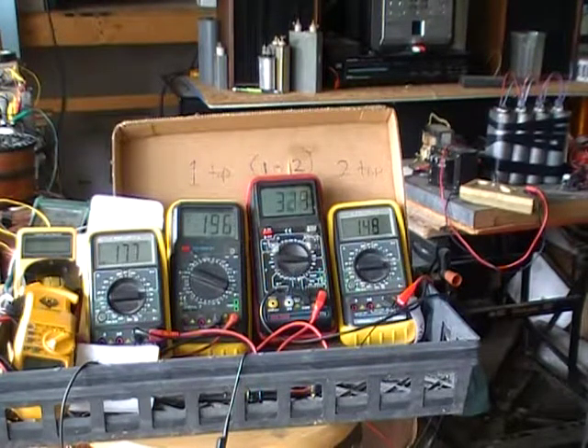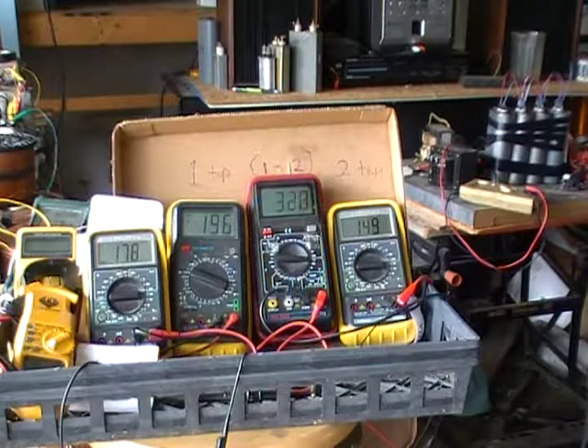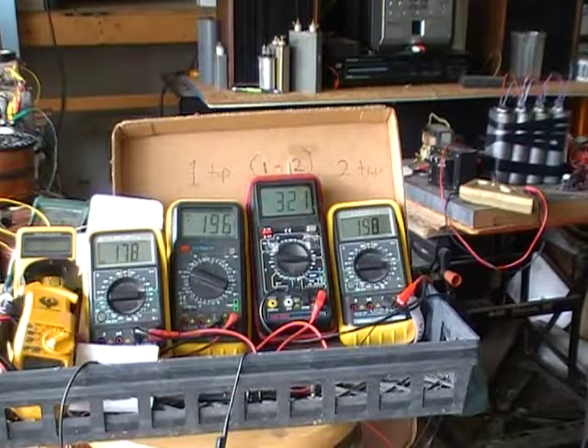Note that even without the field turned down, we have generated some 320 volts between 196 volts and 149 volts. The 149 volts is coming from the back, the 196 from the front, and if you apply the law of cosines to that, you'll find out that's about a 130 degree phase angle. It's not 120 degrees because the mutual induction between the systems has actually changed the phase angle.